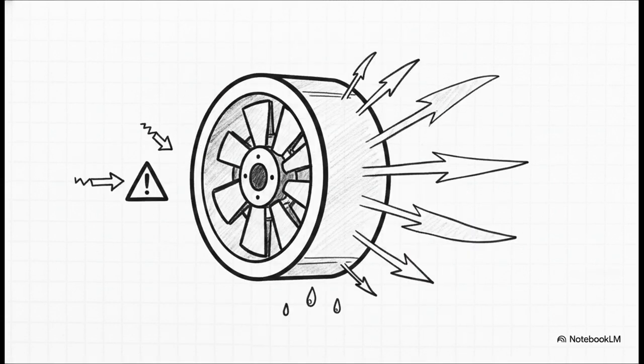In the other corner, we have the centrifugal, or turbo compressor. Instead of squeezing gas, it uses a high-speed rotating impeller to just fling the gas outward, creating extreme centrifugal velocity. That fast-moving gas hits a diffuser, which slows it down, converting all that kinetic energy into massive pressure. This water-cooled powerhouse gives you ultra-large capacity.